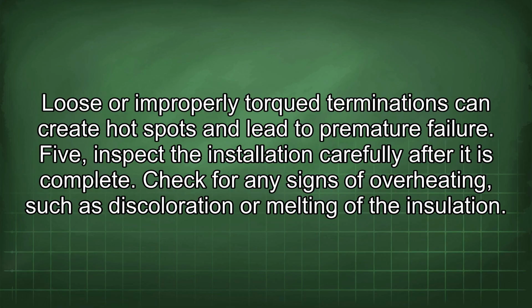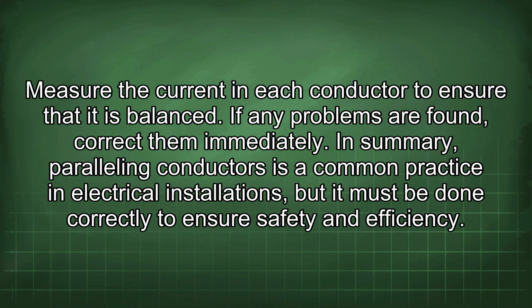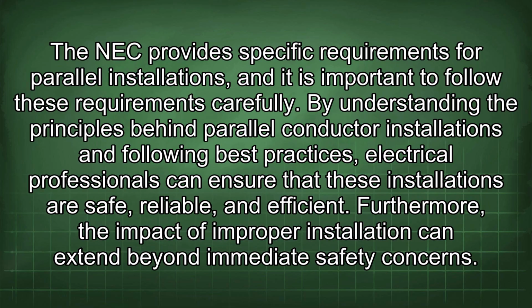5. Inspect the installation carefully after it is complete. Check for any signs of overheating, such as discoloration or melting of the insulation. Measure the current in each conductor to ensure that it is balanced. If any problems are found, correct them immediately. In summary, paralleling conductors is a common practice in electrical installations, but it must be done correctly to ensure safety and efficiency. The NEC provides specific requirements for parallel installations, and it is important to follow these requirements carefully.